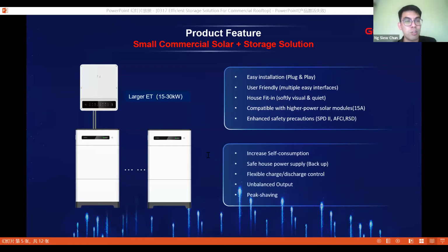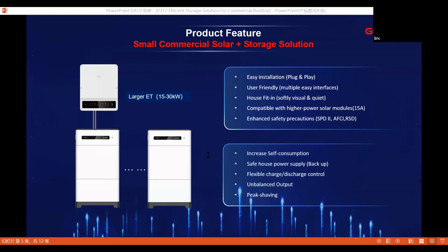So basically, you are referring to the power factor correction capability of our system. Eric, maybe you want to talk about this? If you install a PV system in your commercial rooftop, the power factor of your factory will decrease. Because most of the load consumption is provided by the PV power and the battery, you do not get much active power from the grid, but you still get the same reactive power from the grid, so the power factor will decrease.